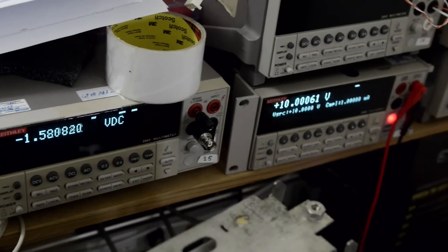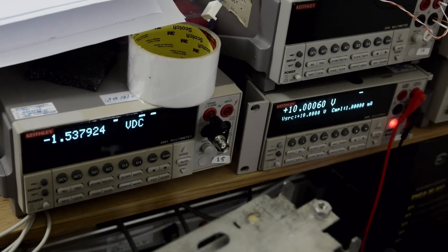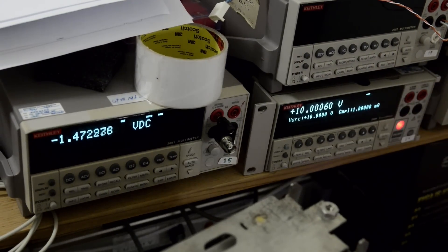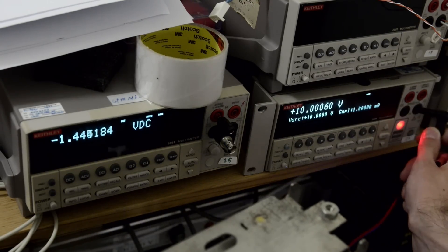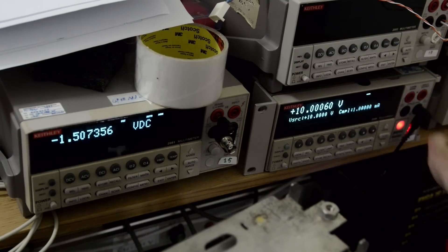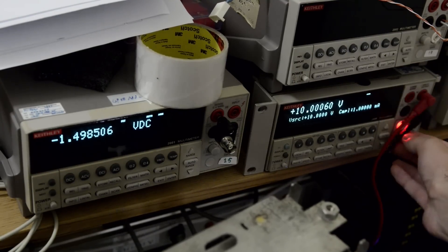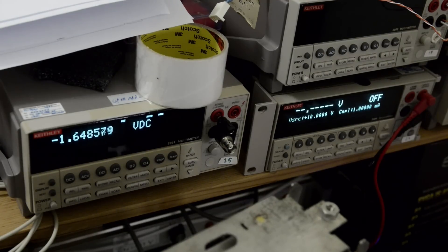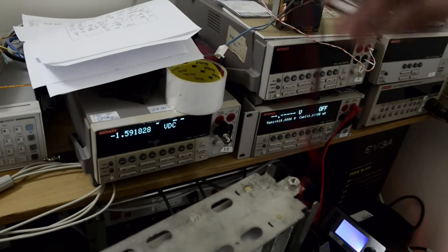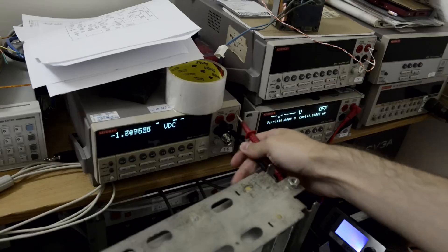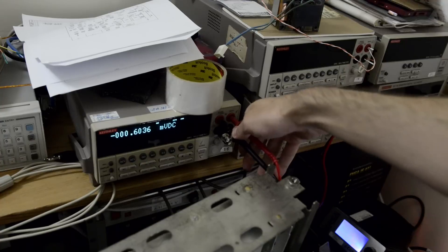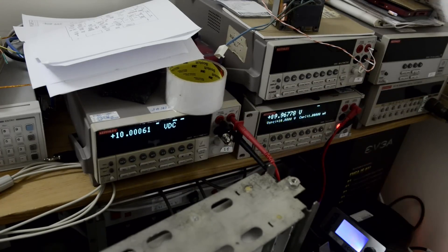By using my Calibrator 2001. So I'll disconnect these two wires and connect these two wires. No cheating here. I'll connect to my Keithley output on.